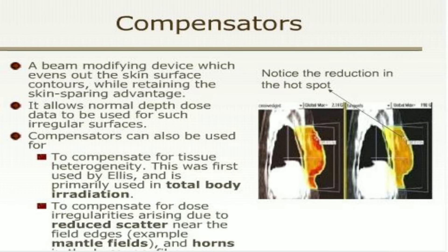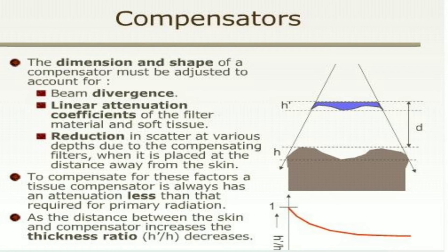A compensator is a beam modifying device which evens out the skin surface contours while retaining the skin-sparing advantage. It allows normal depth dose data to be used for such irregular surfaces. Compensators can also be used to compensate for tissue heterogeneity and to compensate for dose irregularities arising due to reduced scatter near the field edges. The dimensions and shape of the compensator must be adjusted to account for beam divergence, linear attenuation coefficient of the filter material and soft tissue, and reduction in scatter at various depths due to the compensating filter when placed at a distance away from the skin.